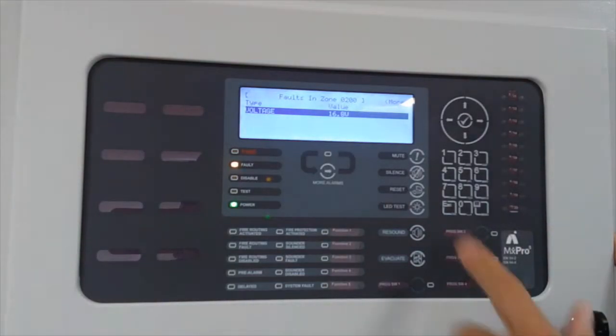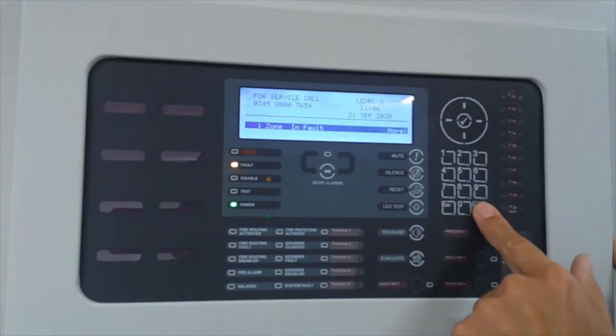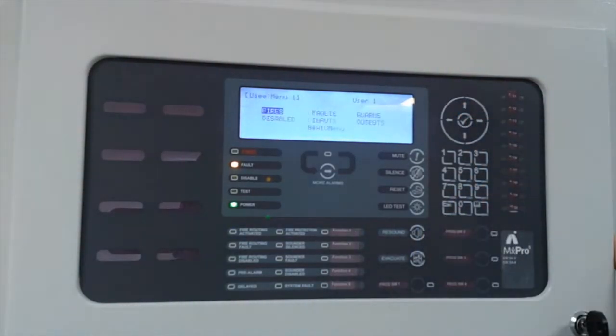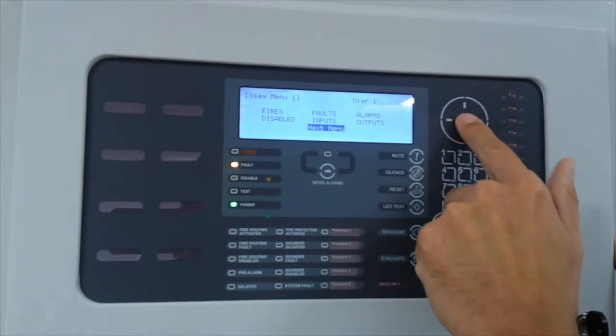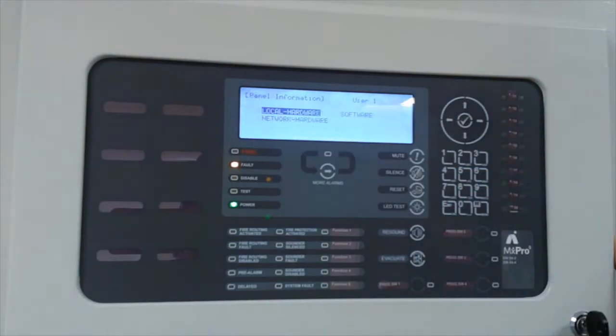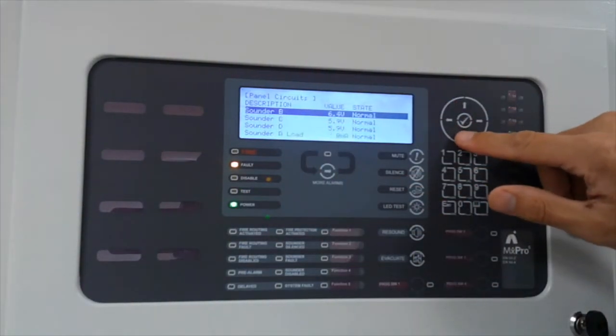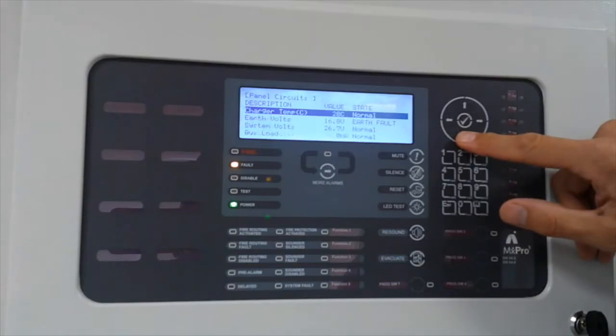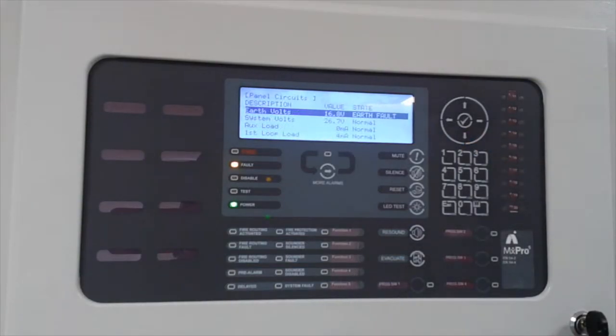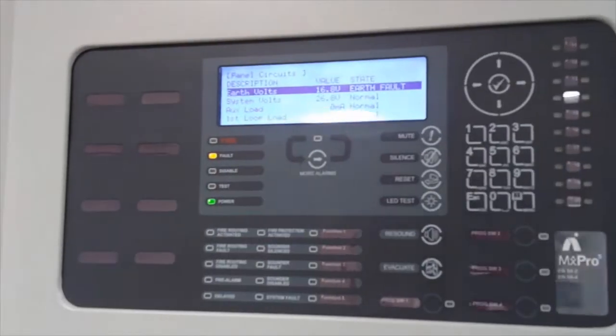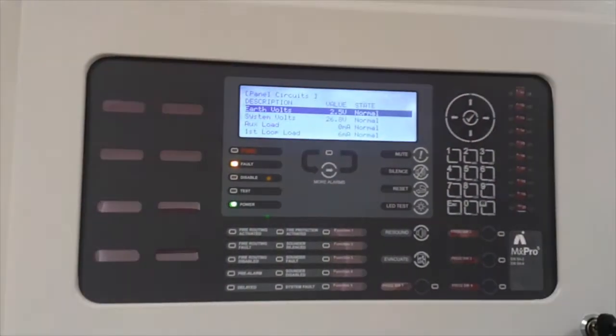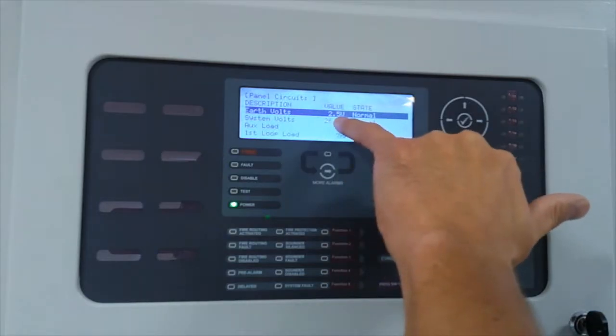So what do we do? We know we've got an earth fault on the system. Press your menu button, select the view option, scroll and find your panel menu. The panel is built with its own multimeter. We can see our sounder circuits in normal operation, scroll down to battery circuit charging voltage, temperature, and we've got an earth fault: 16.0 volts. This is a positive conductor to ground. The normal reading is 2.5 volts.